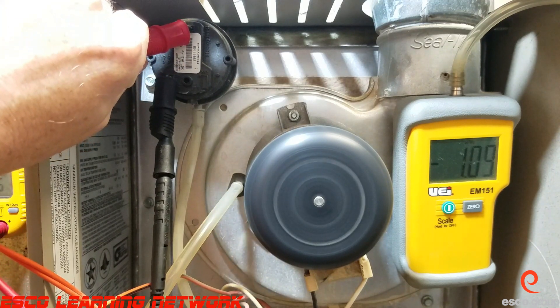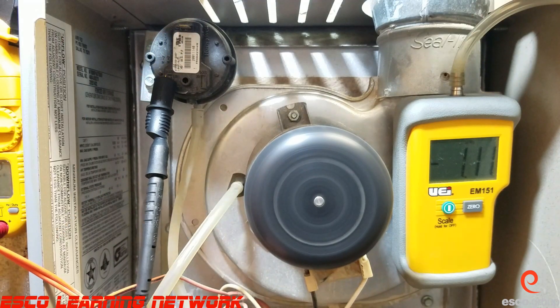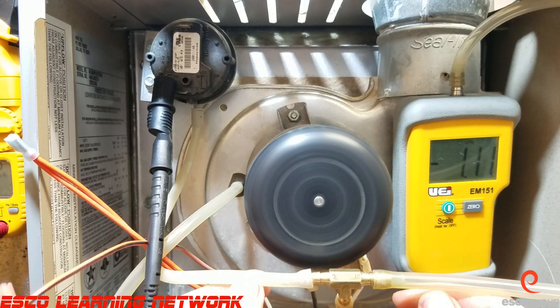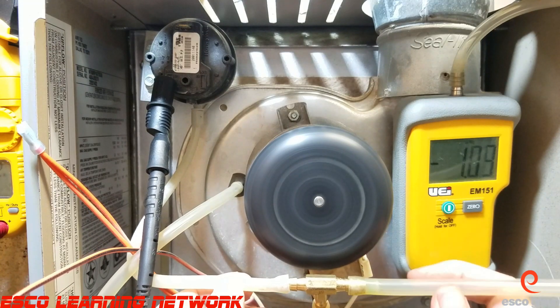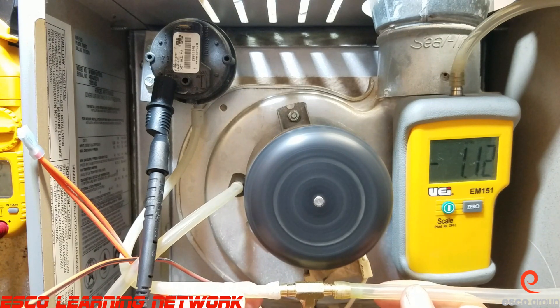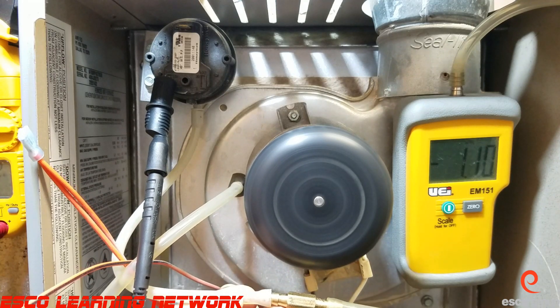So this switch is good. Again, we're using a T-setup here so that we can have the manometer in series with the pressure switch. Don't forget to put it all back together the right way when you're done. This has been the workbench series — thanks for tuning in, and we'll catch you on the next one.